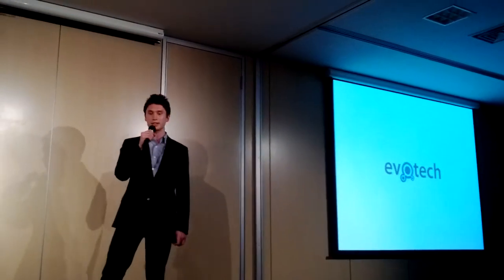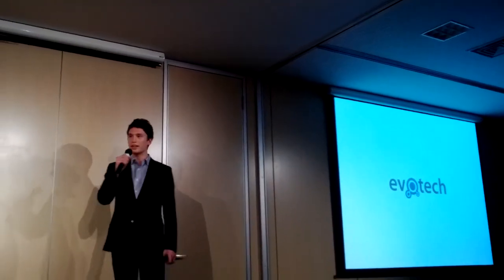Evotech is a company aiming to radically redesign endoscopy to make it affordable and available to physicians operating in resource-constrained settings. Our latest clinical prototype was developed together with designers from IDEO and engineers from MIT. It's constructed of only off-the-shelf components that you can find in any electronic store. And it is connected to a laptop and runs through the laptop battery.